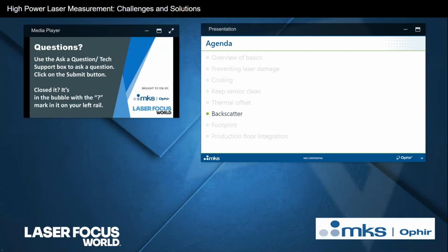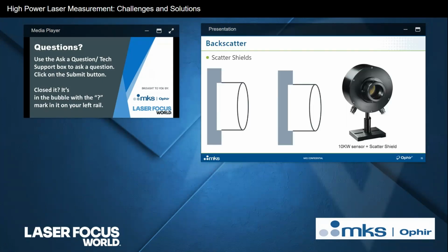Let's just say a few words about backscatter. Typical laser sensor absorbers have absorption on the order of 90-something percent, and the other 5, 10, whatever percent, the number also depends on wavelength, gets reflected back. Usually the absorbers have a matte surface, which means that backscatter is diffuse. But when we're talking about tens of kilowatts, that's still a good couple kilowatts that are being backscattered back out into the room. Okay, diffusely, that's true, but still.